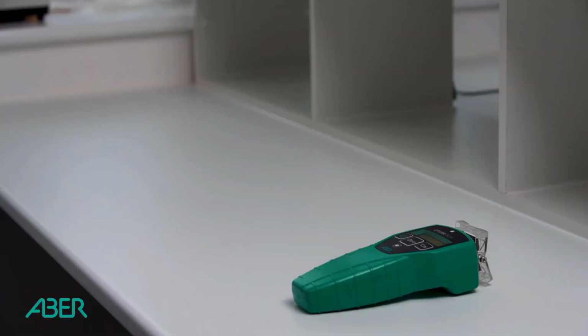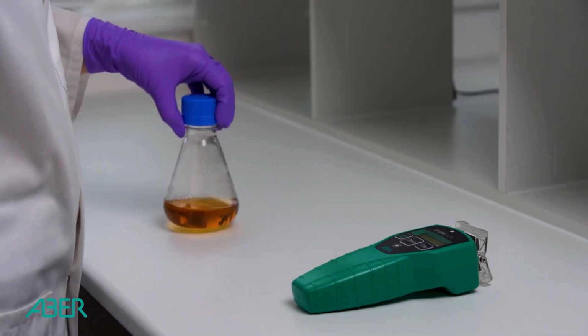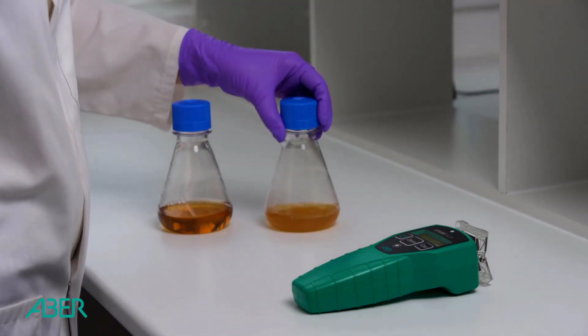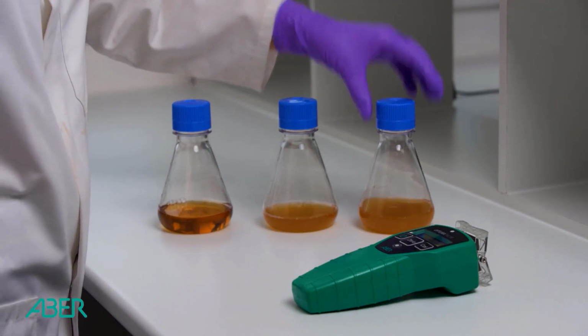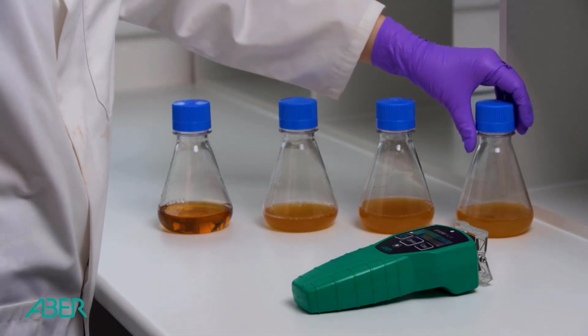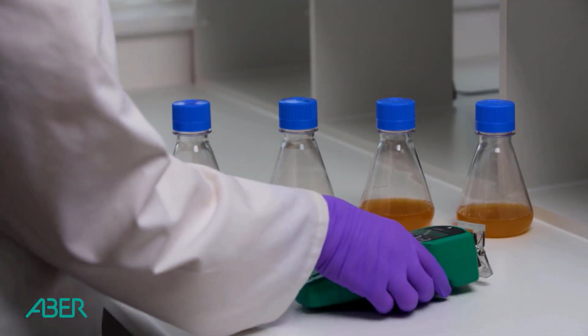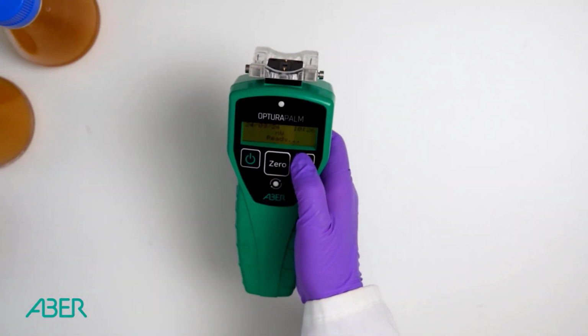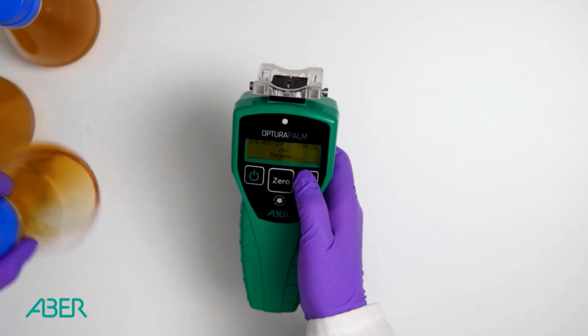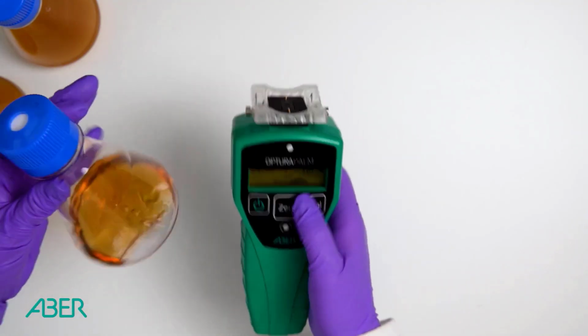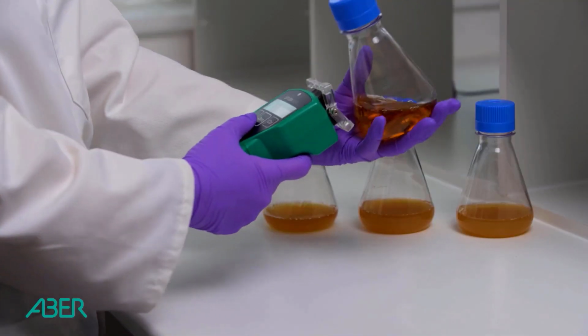If you would like to generate your own biomass calibration, you can do this by either using the palm to monitor your flasks that you already have going, or you can do this by taking readings in a dilution series. Here I have multiple flasks containing different concentrations of yeast. I already know the offline values and have those written down. A biomass calibration should be made for a particular cell type, flask and media type. If you change up one of these parameters, it is advised that a new biomass calibration is made.